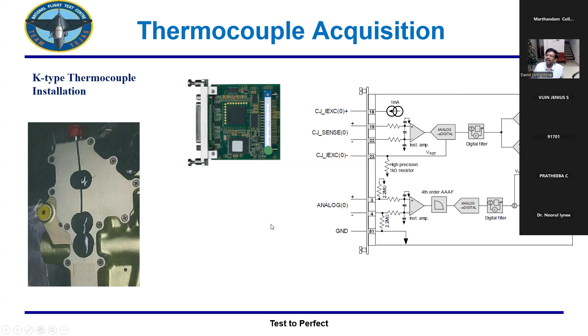Because the junction where it has to be measured in the engine is called the hot junction, or the junction measurement point, right? So this cold junction, when all this connector is at the same temperature, this temperature should be known, right? So there is the equation for cold junction compensation. Then this millivolt will be mapped to the temperature with the cold junction compensation value, right? So this is the function of this module, right? So a sample case I have taken.